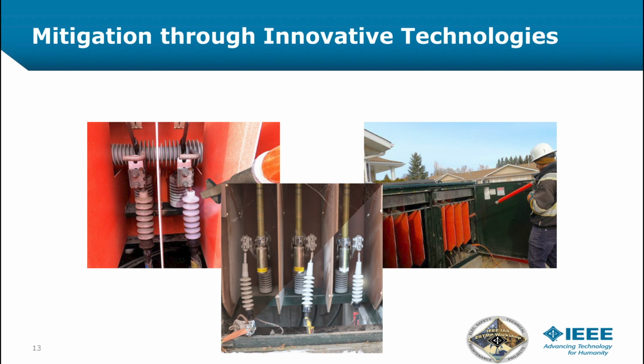The stress cones that are in here were contaminated over time with dust and dirt and contaminants from the atmosphere, and he's blasted them clean, and you can visually see the difference between the old contaminated bushings and the brand new cleaned up ones.